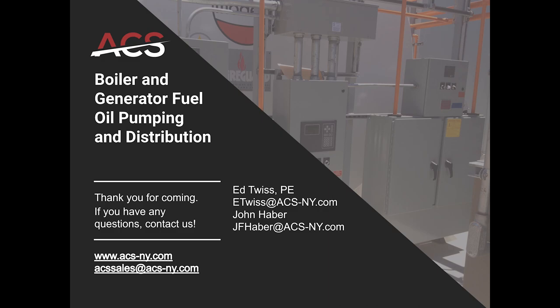Great. Next question is, is it safe to be overly conservative when sizing suction line on a pump skid? Sizing the suction piping is critical. If you size the pipe too small, you're going to have too many friction losses, and you'll have problems getting the oil into the pump, and you're going to have cavitation. If the pipe is too large, we're talking very small pumps here, gallons per hour, and it's very hard to prime a large pipe and to get that oil moving.